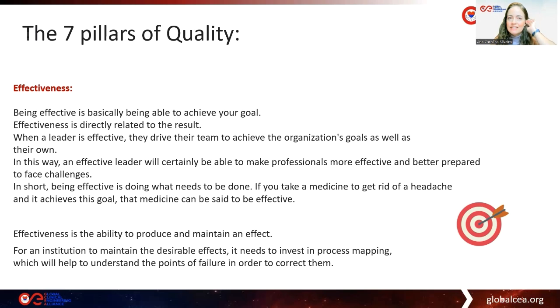Let me bring an example. Once I was asked about a phototherapy that was not working well in an institution because the baby with jaundice was not getting better, and the director wanted to buy a new phototherapy. I analyzed the case, and the problem, of course, was the quality of the lamps. We changed the lamps for lamps with better quality, and the next day the baby was discharged.